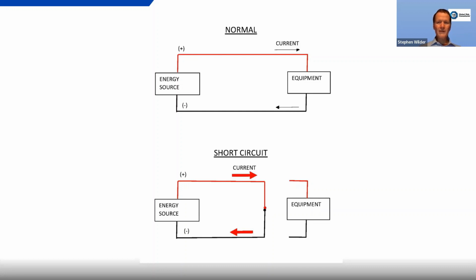But what if it's 20 million amps? The breaker has a limit on how much current you can put on it before it just explodes. And that's the interrupt rating. We do the short circuit calculations to make sure that the calculated short circuit current does not exceed the interrupt rating of the electrical equipment.